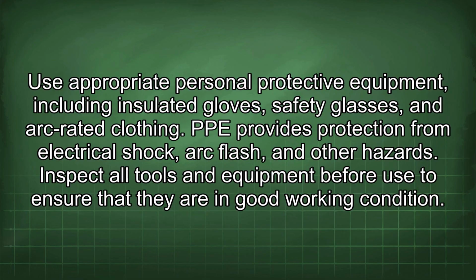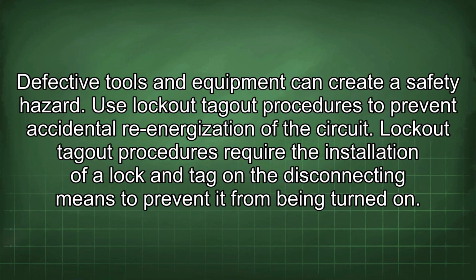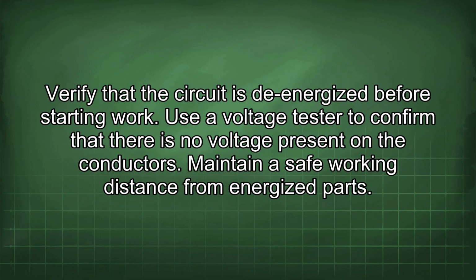Use appropriate personal protective equipment, including insulated gloves, safety glasses, and arc-rated clothing. PPE provides protection from electrical shock, arc flash, and other hazards. Inspect all tools and equipment before use to ensure that they are in good working condition. Defective tools and equipment can create a safety hazard. Use lockout-tagout procedures to prevent accidental re-energization of the circuit. Lockout-tagout procedures require the installation of a lock and tag on the disconnecting means to prevent it from being turned on. Verify that the circuit is de-energized before starting work.